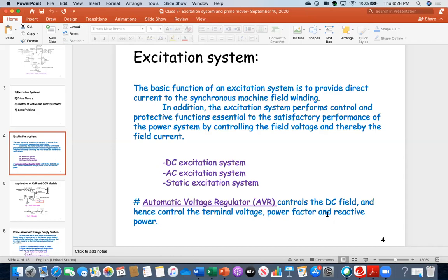Therefore, you see these three variables are analogous: terminal voltage, power factor, and reactive power. Everybody keep in mind, these three are analogous. This means if you change one, the other two will change. If you increase one, the others will increase. If you decrease one, all will decrease. That is the interrelationship among these three variables.